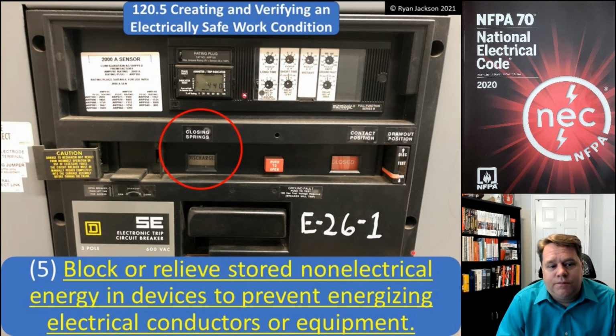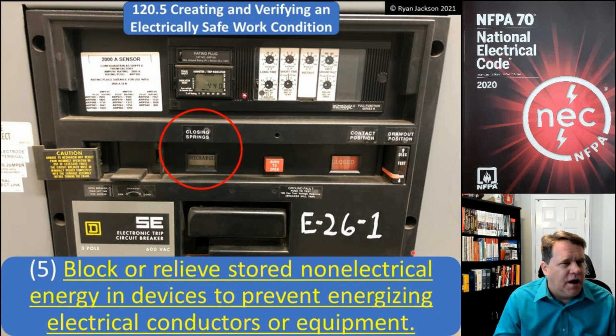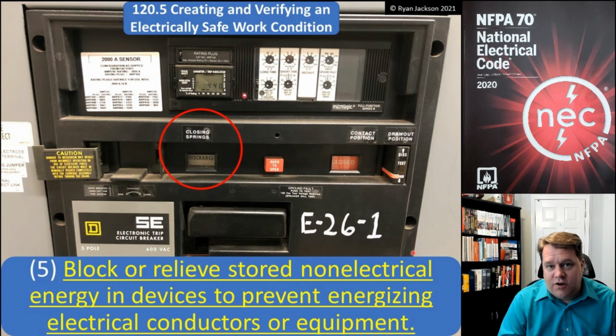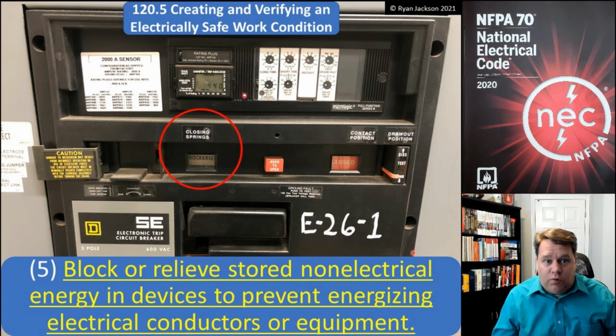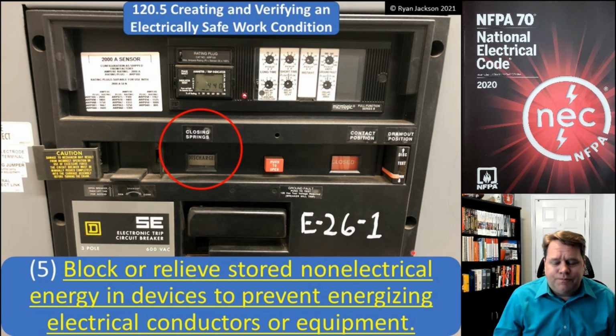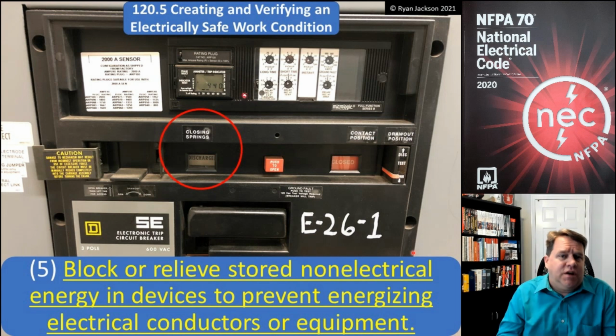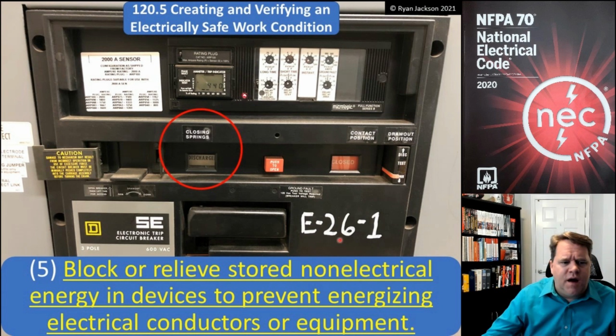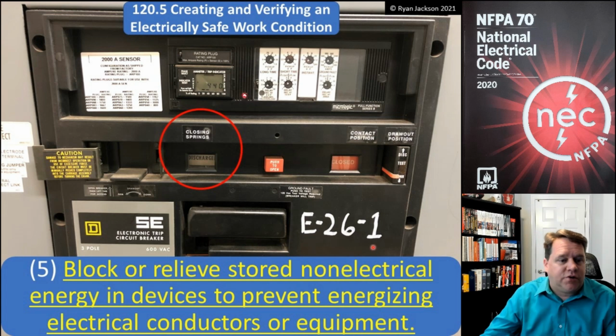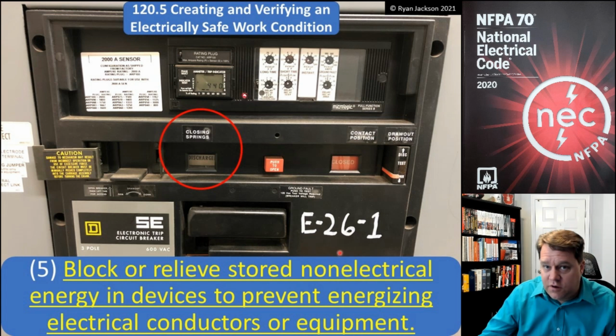But when it comes to establishing and verifying an electrically safe work condition, we definitely need to release any stored electrical energy. And item 5, which was clarified in the 2021 version, we need to block or relieve any stored non-electrical energy in devices to prevent energizing the conductors or equipment. Previous versions simply said to block or relieve mechanical energy. Well, mechanical energy could be a lot of different things. That could be a water valve potentially, or gears that could possibly rotate. Those are definitely hazards, but they're not necessarily electrical hazards, and the scope of 70E is electrical hazards. So we're clarifying: let's block or relieve stored non-electrical energy in devices to prevent energizing the equipment.